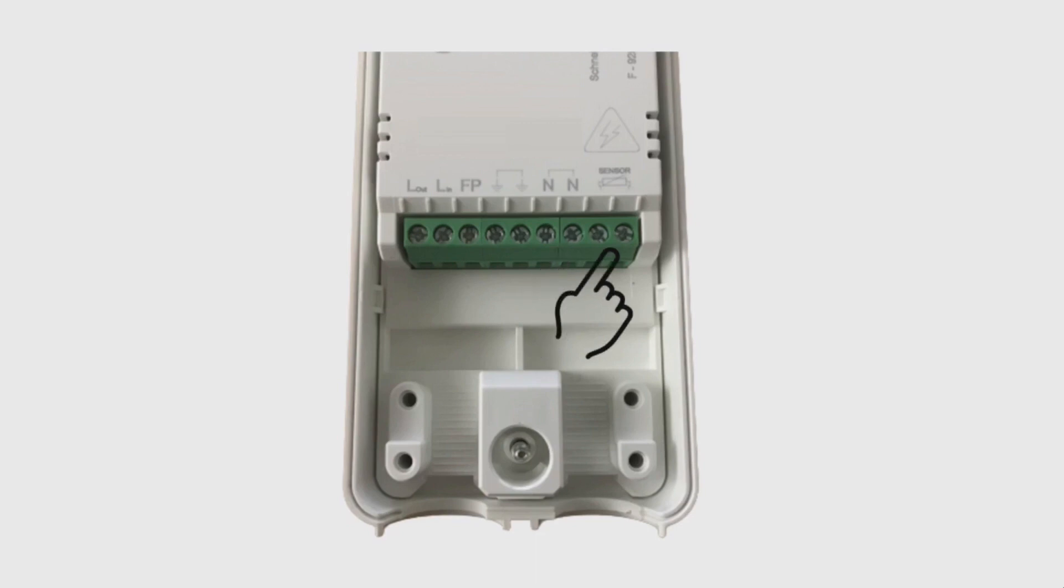Finally you have the two terminals for the connection of a floor sensor. If you're going to be using this with electric underfloor heating, it's mandatory that a floor sensor is connected to prevent injury. Moving away from the terminal rail, the cable clamps here secure the incoming and outgoing cables.